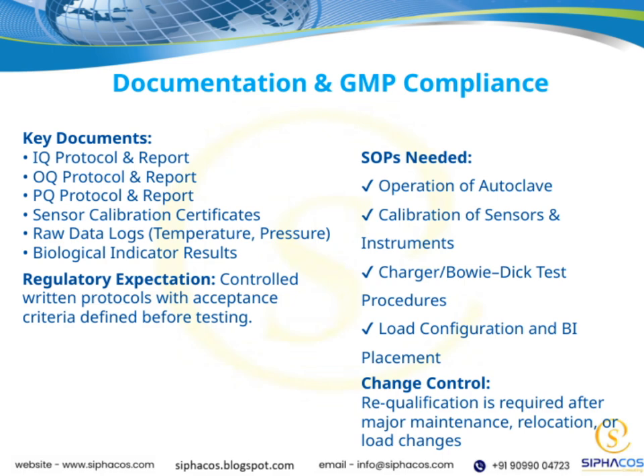From a regulatory perspective, it's vital that we follow controlled written protocols with clearly defined acceptance criteria established before testing begins. This helps ensure consistency and compliance throughout the process. Now, regarding documentation and GMP compliance, it's important to develop and adhere to SOPs for key activities. These include operating the autoclave, calibrating sensors and instruments, performing Bowie-Dick tests, and managing load configuration and biological indicator placement. Each SOP ensures that procedures are standardized and consistently followed.